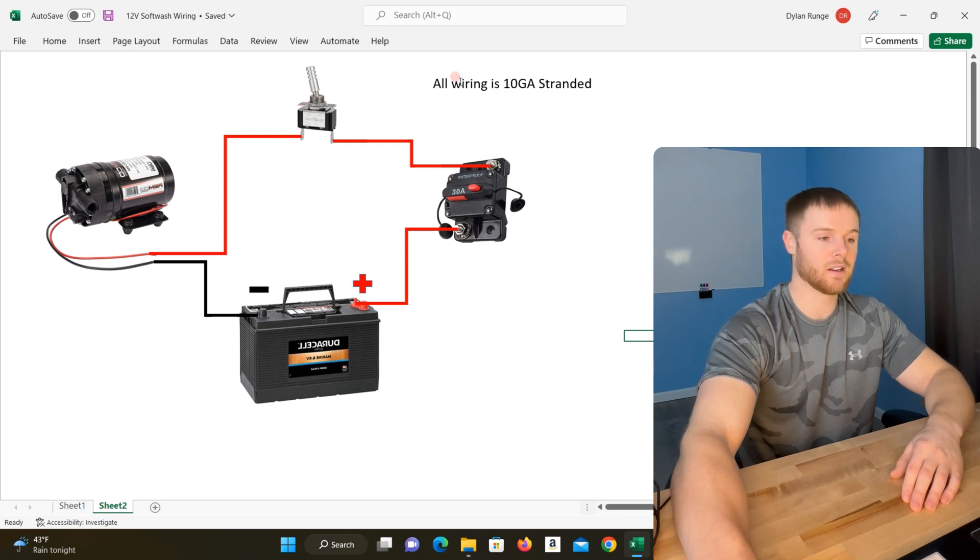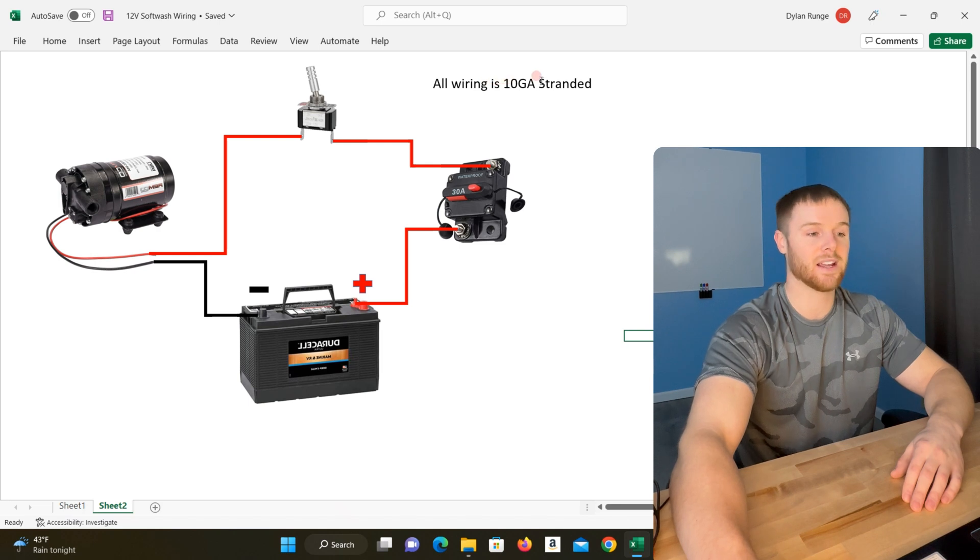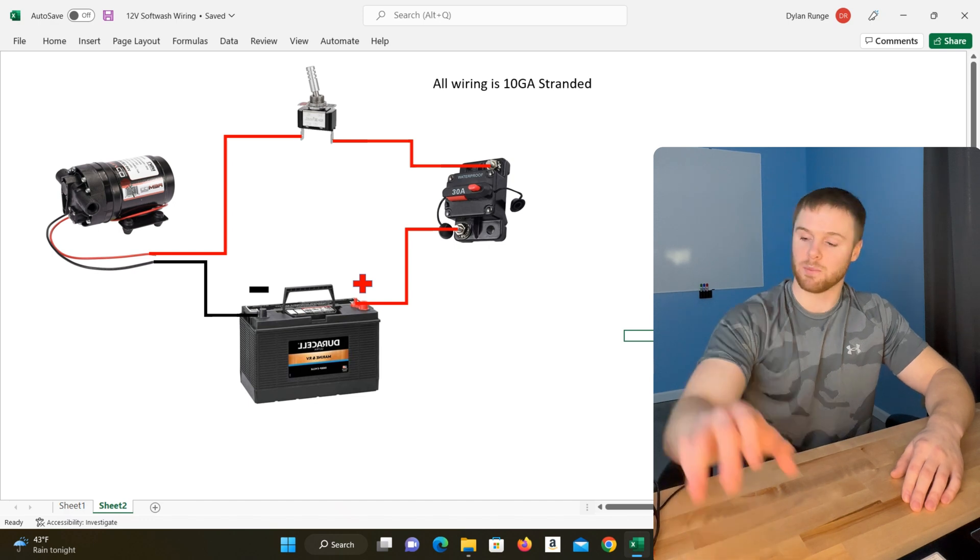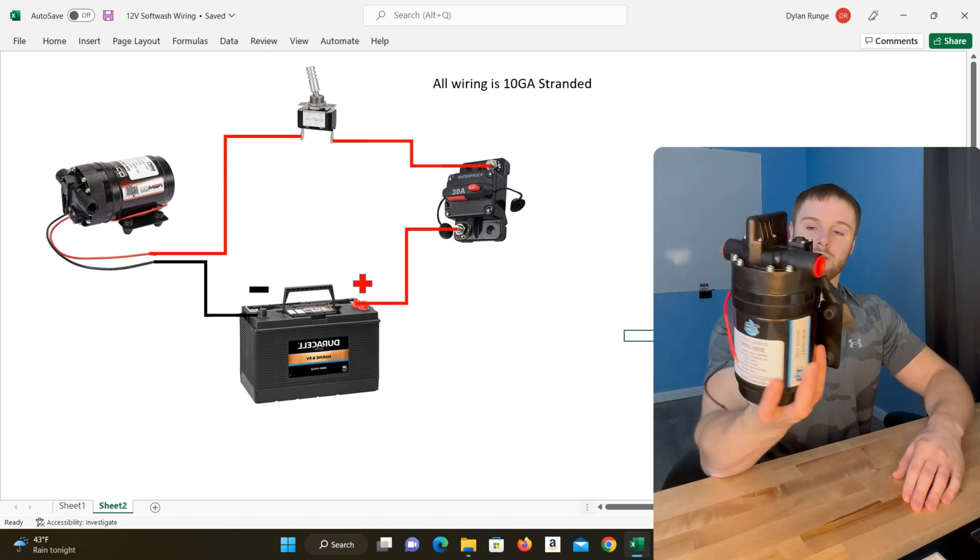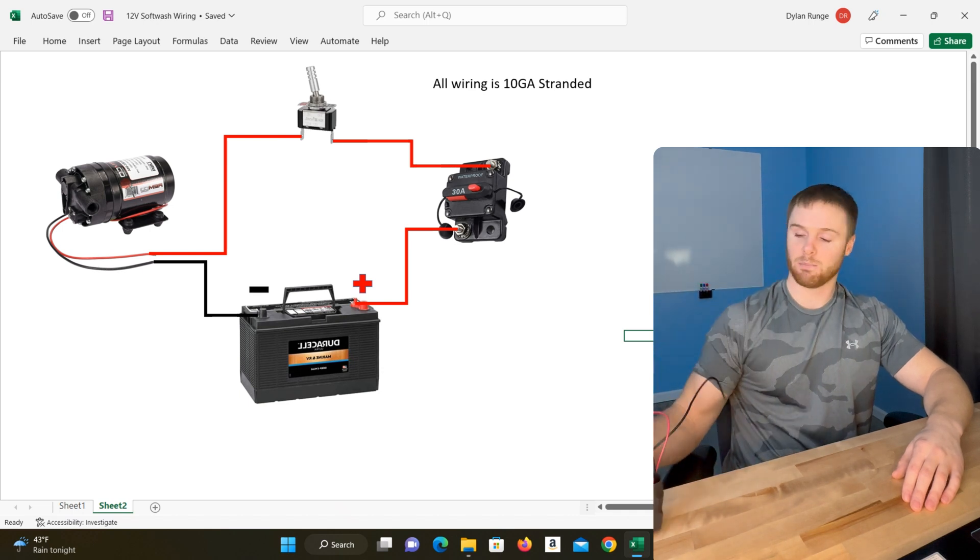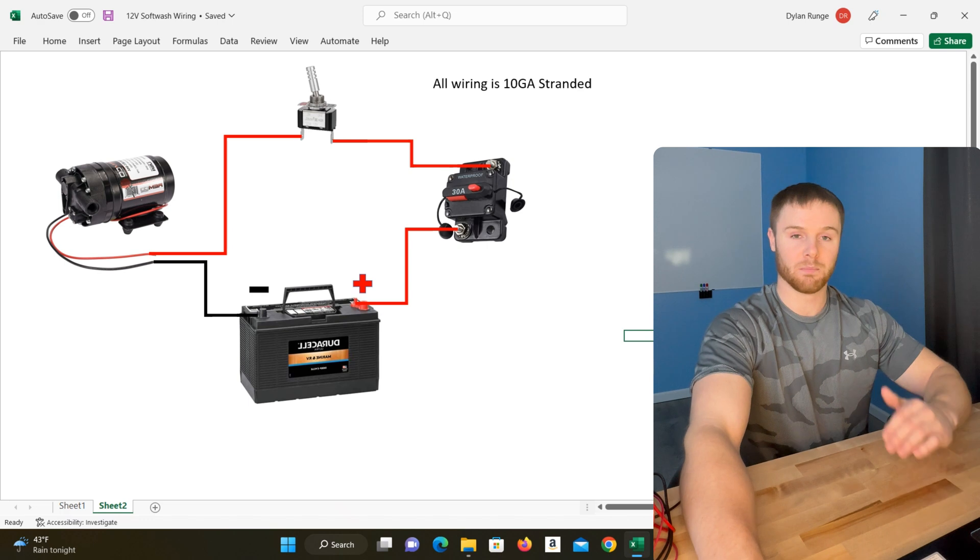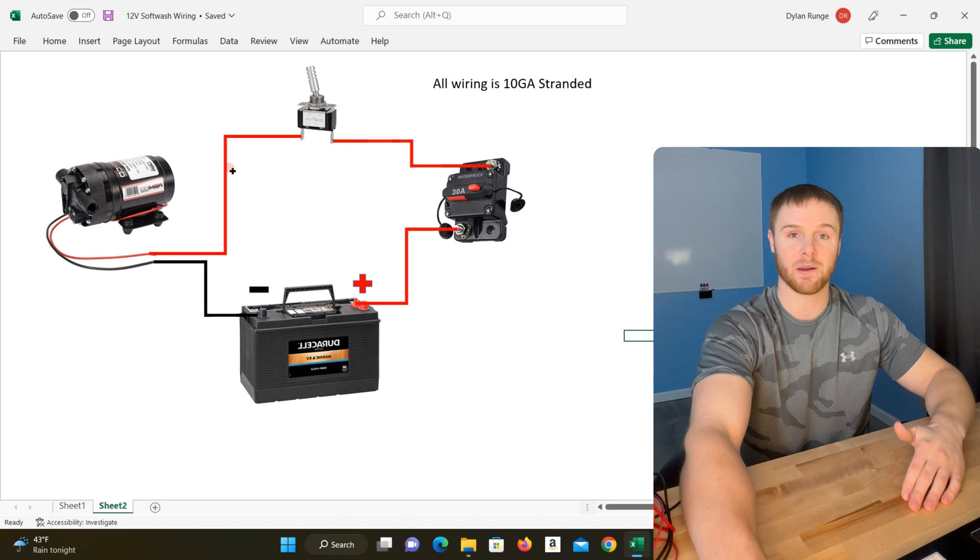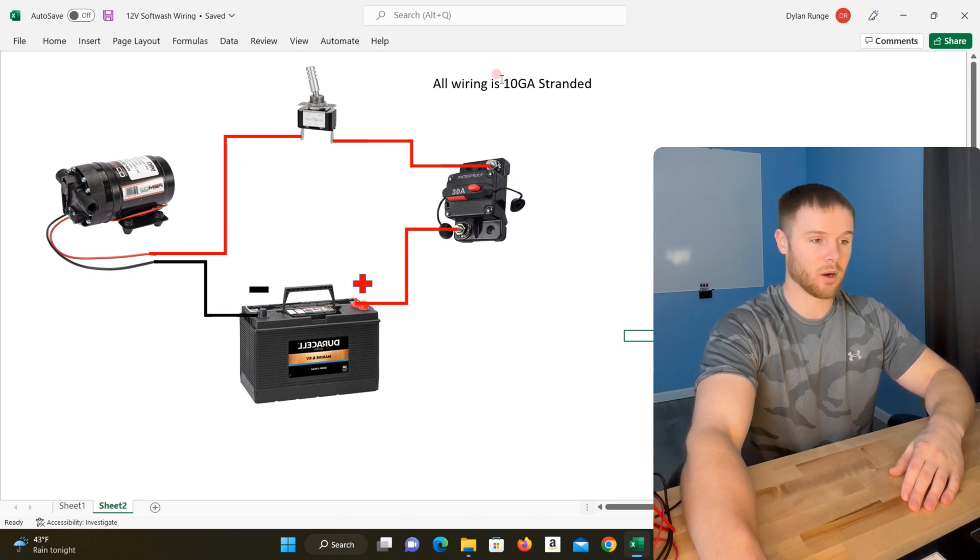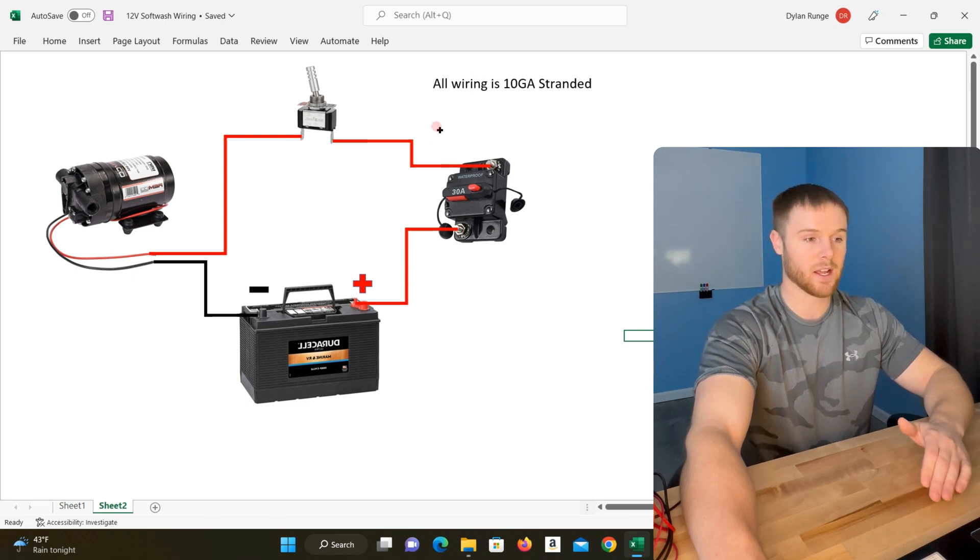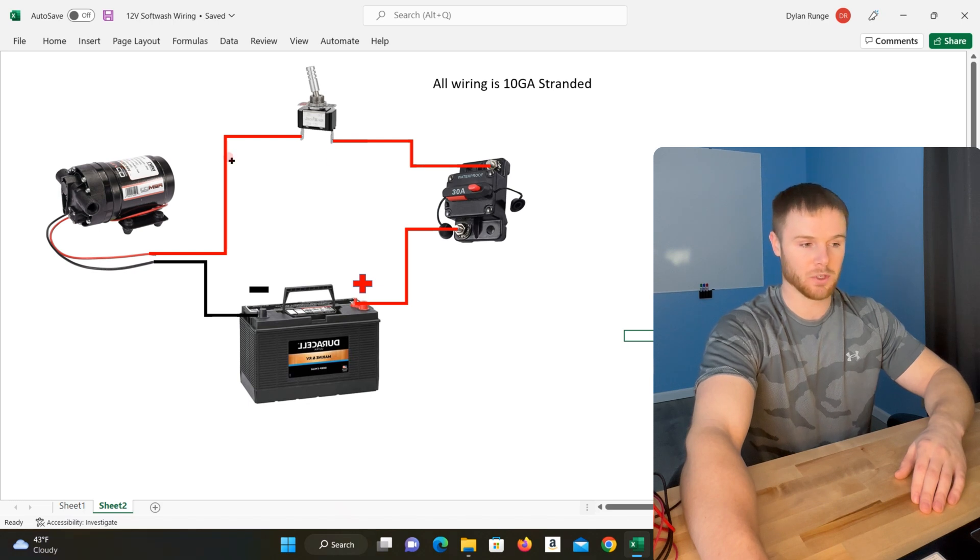One other thing to note, we do use 10 gauge stranded in this application because this pump, this specific pump that I have, requires or states that it has 24 amp max peak current. If 24 amp is the peak, then we want to make sure that our wire can actually handle that many amps. That's why we need to size our wire appropriately. 10 gauge stranded is actually rated for 30 amps, so that's above our max current of our pump, which is good.